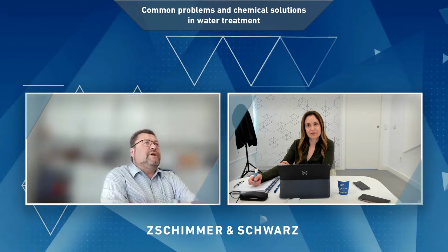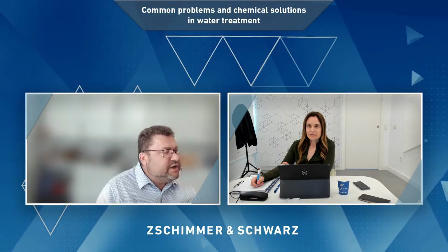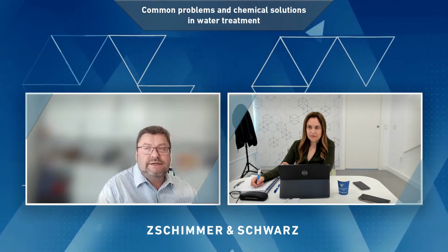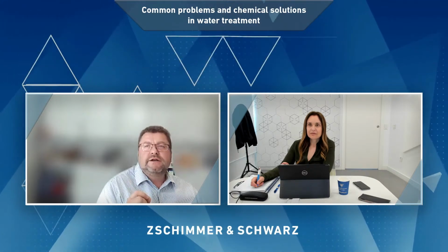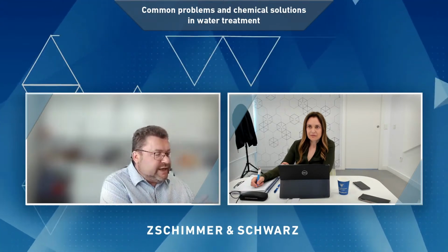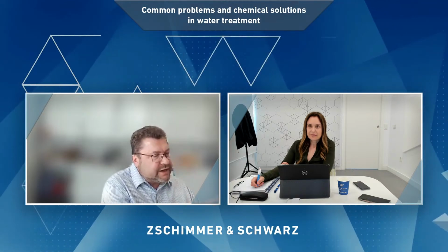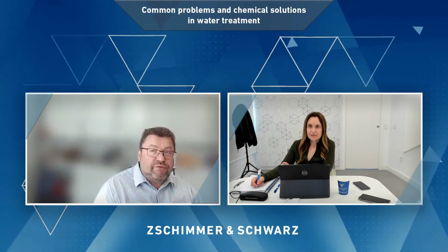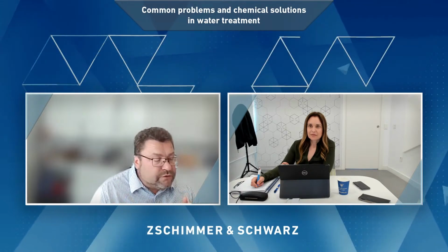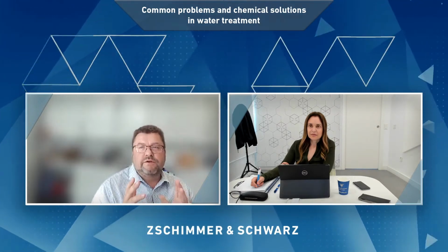Also, as we are equipped with a laboratory where we are able to analyze the behavior of chemistry in contact with supersaturated systems, so basically with water treatment questions, we miss one important share to operate this kind of software, because this software is based on both the experience from the chemical point of view, where you calculate how an antiscalant interacts with calcium carbonate, for example, and the practical experience from operating the systems, operating a reverse osmosis facility with a defined water quality, with defined installation parameters, with defined membranes.